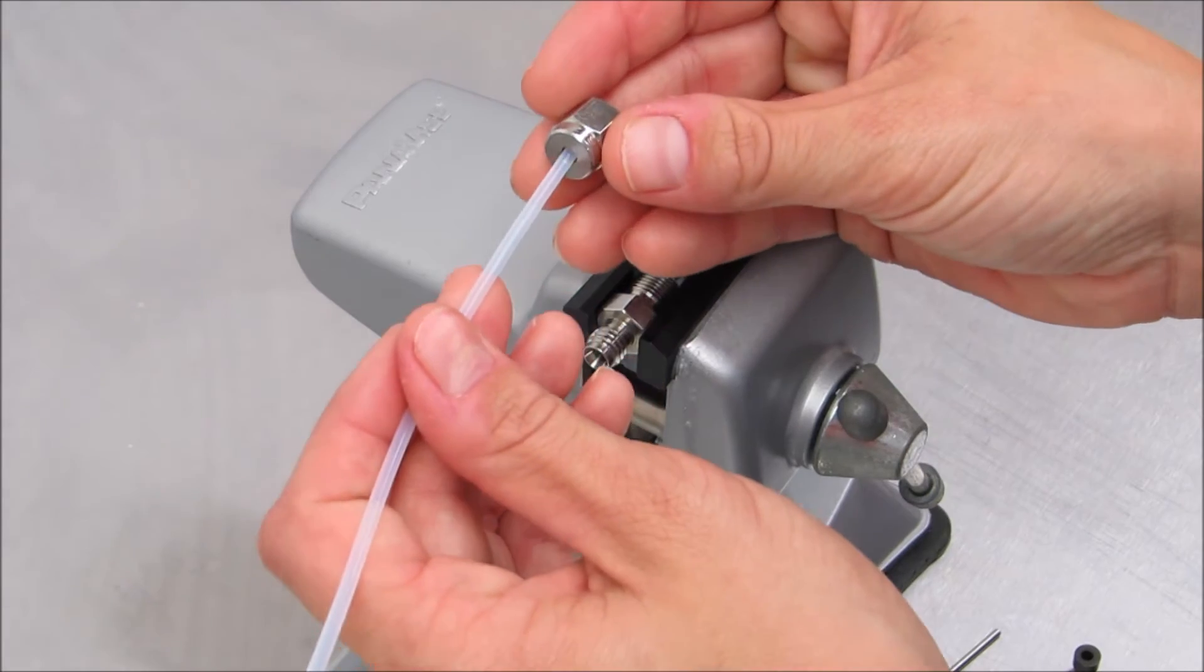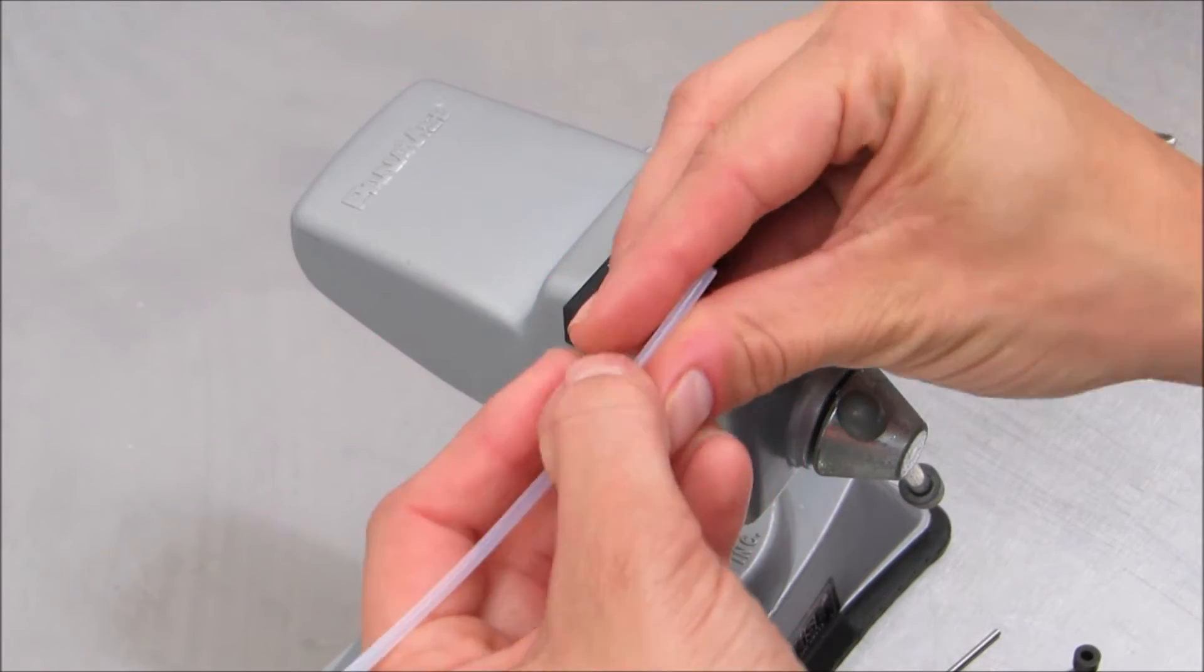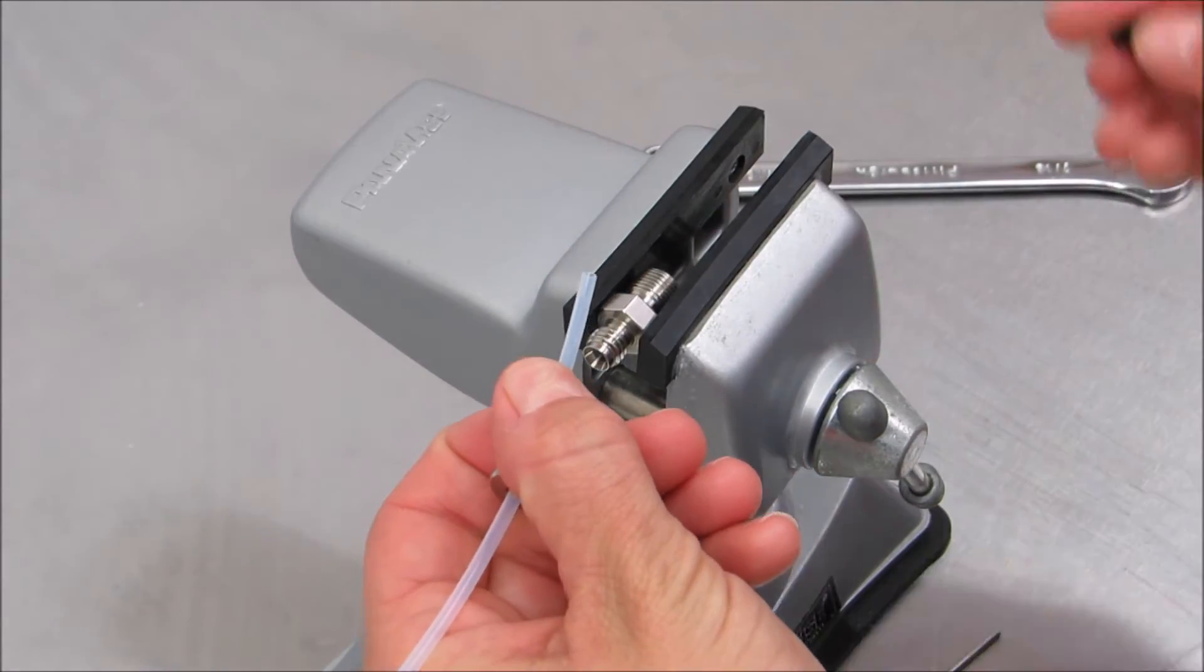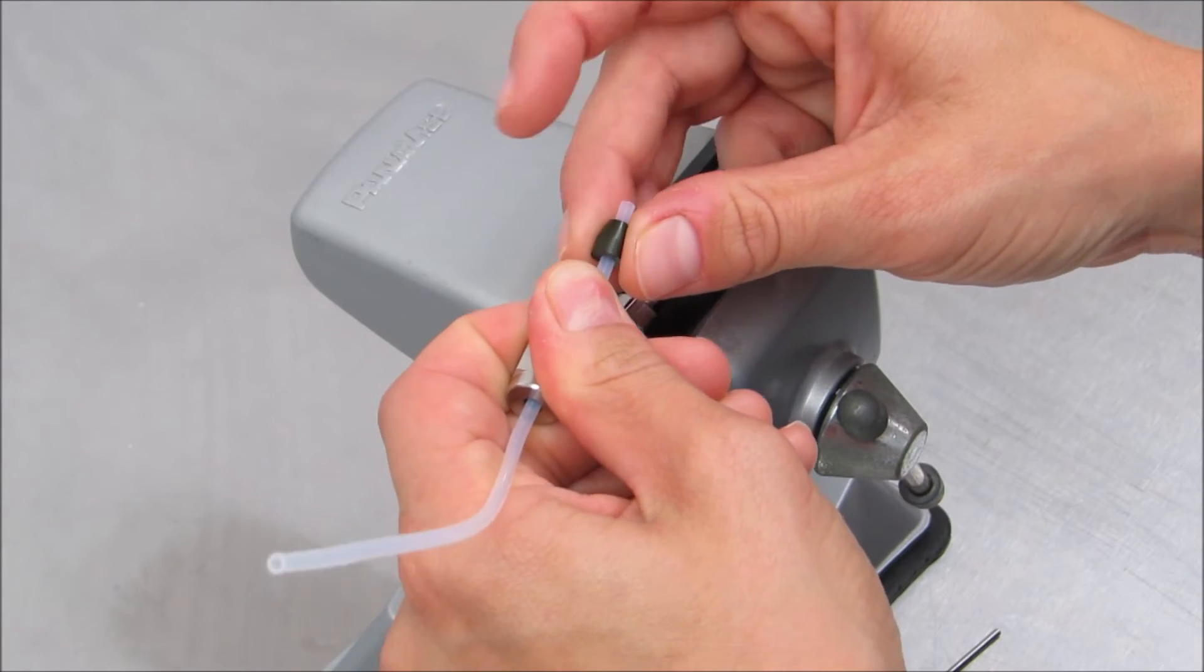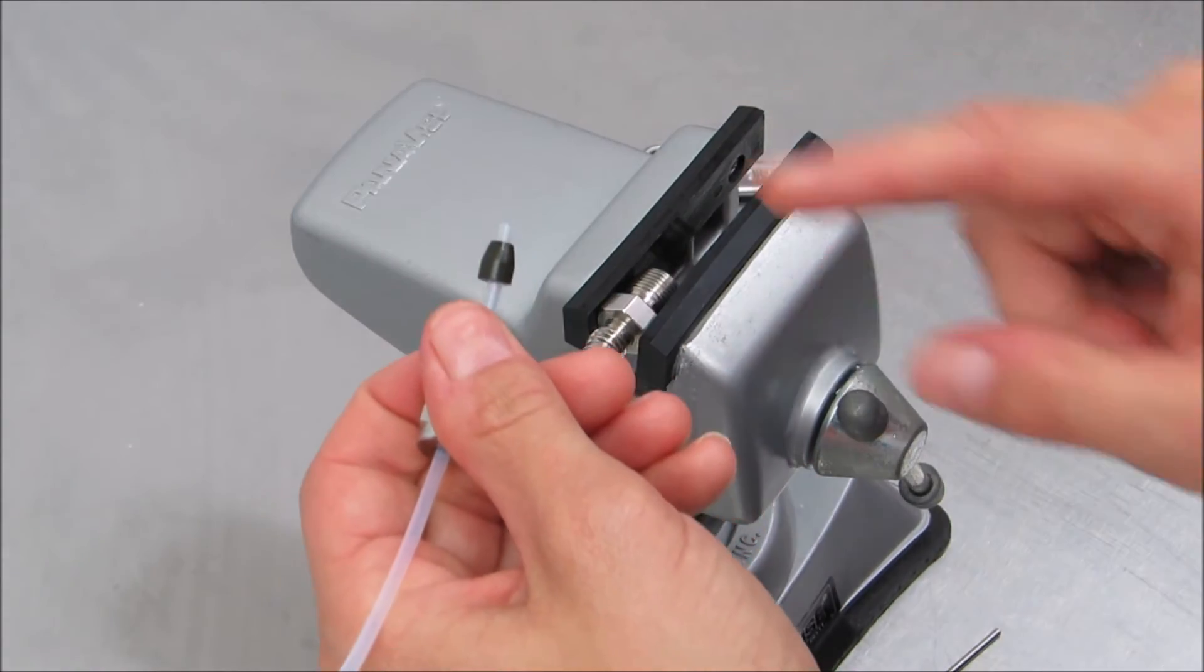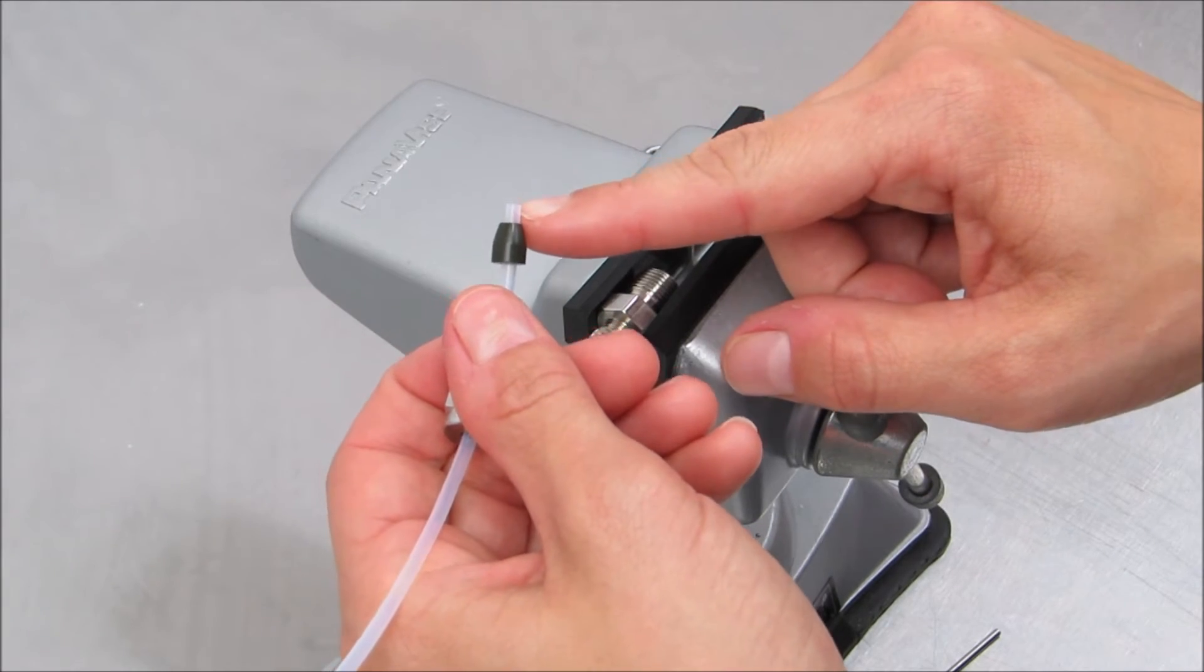First, slip the compression nut onto the PTFE tubing. Then, insert the PTFE tube into the ferrule. The tubing should protrude past the tapered end of the ferrule by about an eighth of an inch or more.